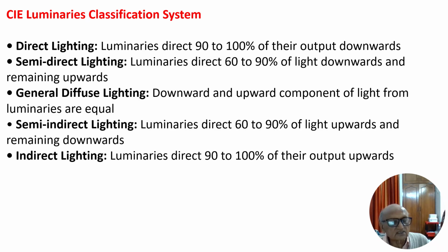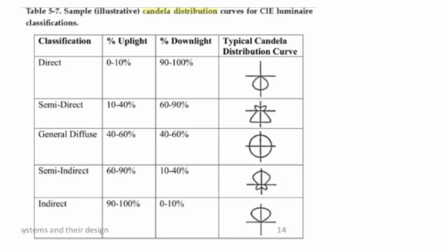These indirect fittings are used in hospital patient care areas. Friends, I am showing the sample candela distribution curve of CIE luminaires classification. The direct fitting takes the light 0 to 10% upward and the remaining downward and has a shape something like an oval.